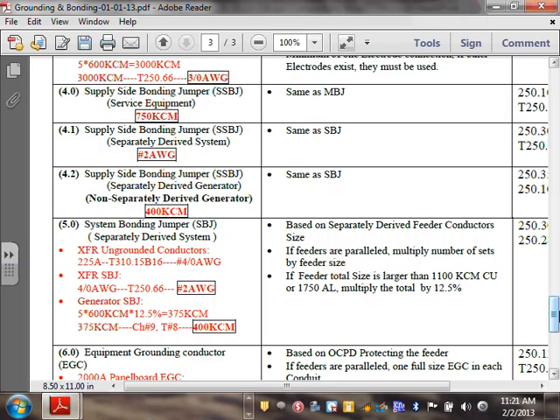Now, don't look at the generator. We're coming to the generator, just because the generator is also another case. Look at just the transformer now. For the transformer, the system bonding jumper is based on a conductor of 4-aught coming out of the transformer and landing in the panel, and I size the transformer to match. I have a number 2, minimum. Any comments, guys? Any questions? Any comments about that? So that's my so-called system bonding jumper.